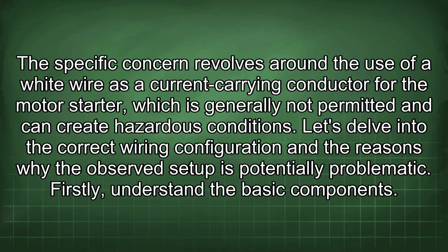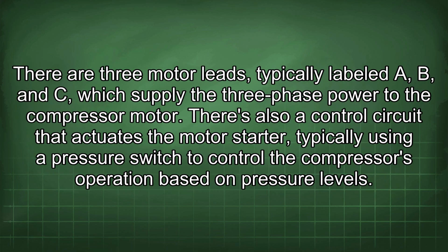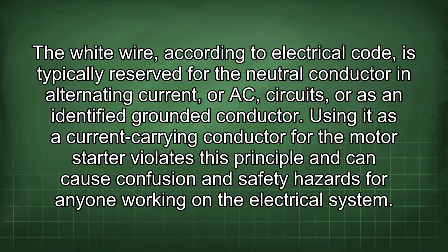Firstly, understand the basic components. There are three motor leads, typically labeled A, B, and C, which supply the three-phase power to the compressor motor. There's also a control circuit that actuates the motor starter, typically using a pressure switch to control the compressor's operation based on pressure levels. The white wire, according to electrical code, is typically reserved for the neutral conductor in alternating current or AC circuits, or as an identified grounded conductor. Using it as a current-carrying conductor for the motor starter violates this principle and can cause confusion and safety hazards for anyone working on the electrical system.